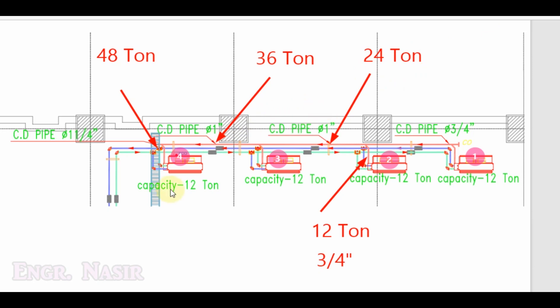Going to FCU4, which also has 12 ton capacity, its branch is 3/4 inch. After connecting all four FCUs, the total capacity is 48 tons. Looking at the table, 48 tons falls in the range from 40 to 90 tons, and the corresponding diameter is 1 and 1/4 inch. In this way, simply add the capacity of all units connected before a given point and look up the corresponding pipe diameter from the table.